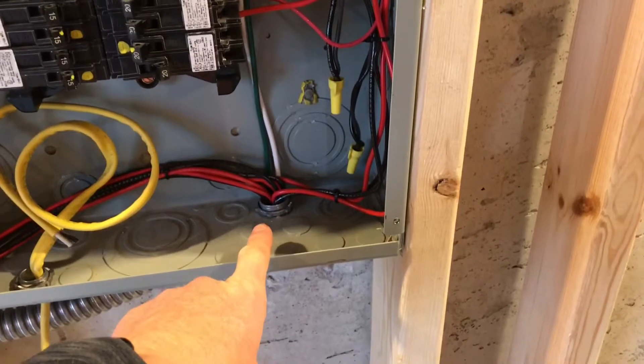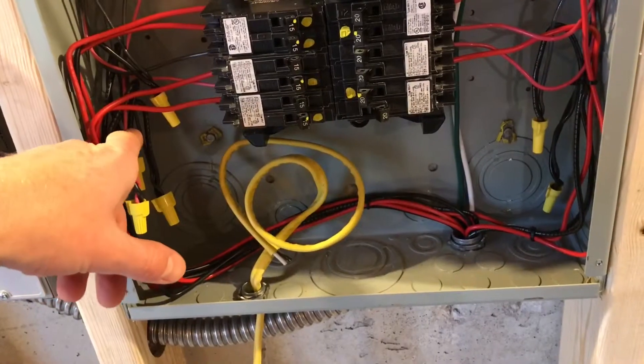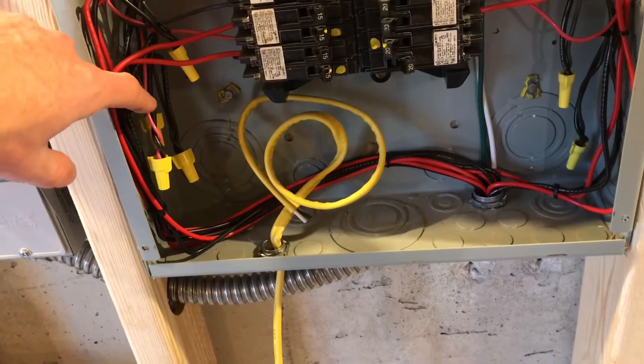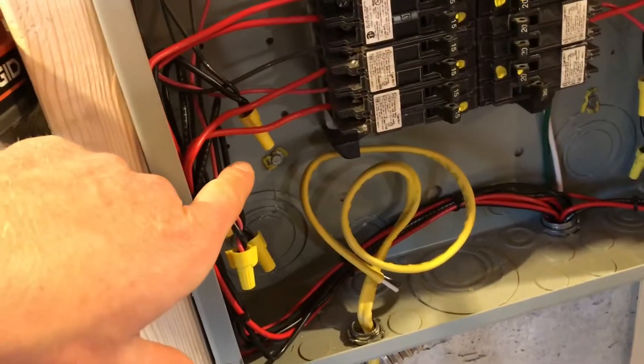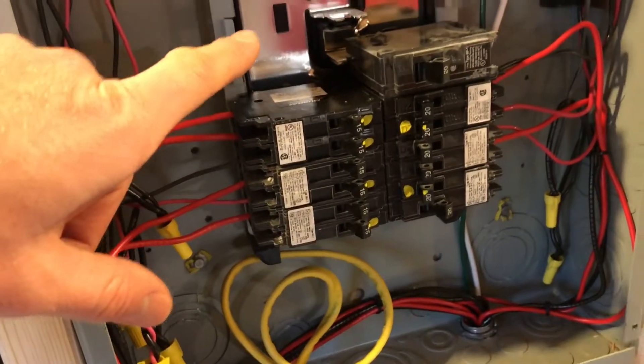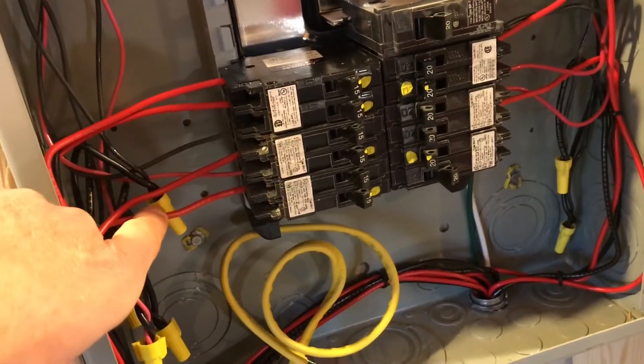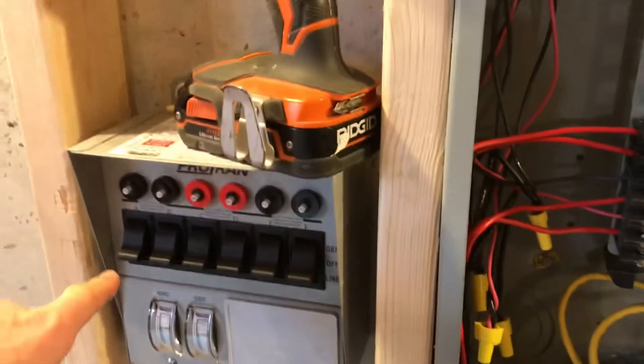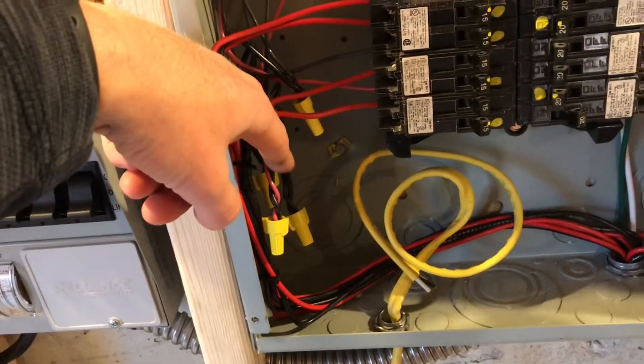Here are the lines coming into the panel from the transfer switch — this is hot out to the circuit. This red and this black wire go from the main panel to the transfer switch. Right now, power is coming into the panel from the line, through the breaker, through the transfer switch, and then back out.